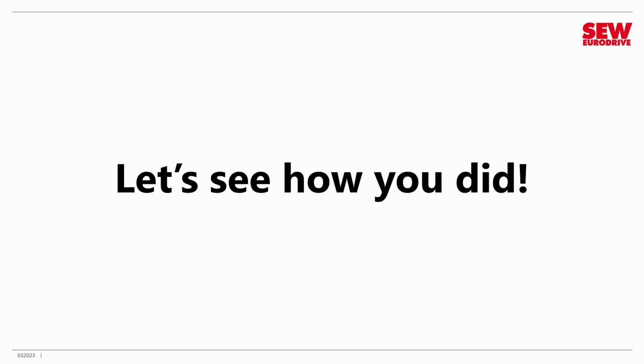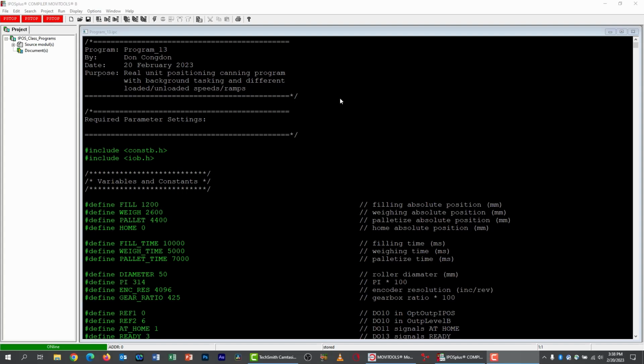All right, well, hopefully that went really easily for you. Let's take a look at my code, and you can compare it to yours. For this program, we don't have a whole lot to do. We're basically taking the previous program, making a copy of it, and then modifying it so that its positioning speeds and ramps differ for the loaded and unloaded condition. So in other words, when the carrier is carrying a can, it's going to move more slowly and have a more gentle ramp. When it returns to the home position, it's going to basically do it as fast as possible.